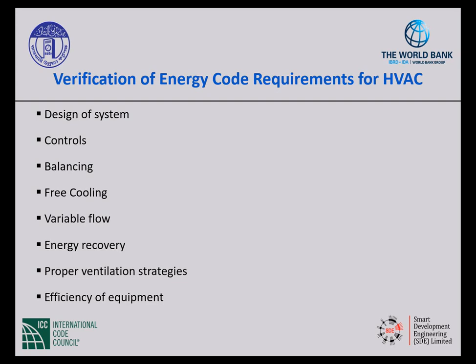For those variable flow pieces of equipment, is it a VAV system? Do they have their 50% of the design flow rate there? There are different things that we need to look at. If they have those pumps with motors over 5 horsepower, are they variable speed drives? Those kinds of things, just verifying that we're meeting these energy efficiency requirements. Energy recovery. This is a tricky one because it says you have to have energy recovery where possible. So that's going to be subjective a little bit, but going out and making sure that anywhere that it was possible, they had their energy recovery systems, again, hooked up and working.